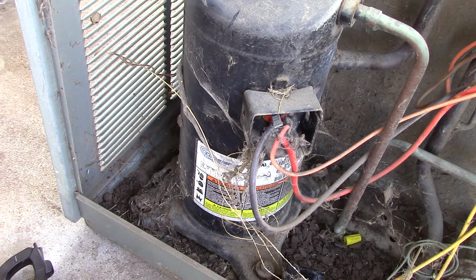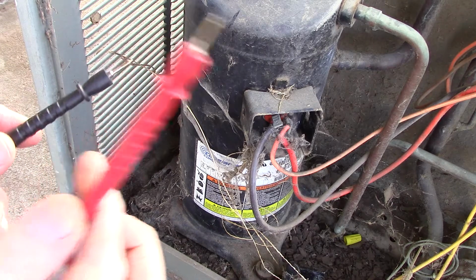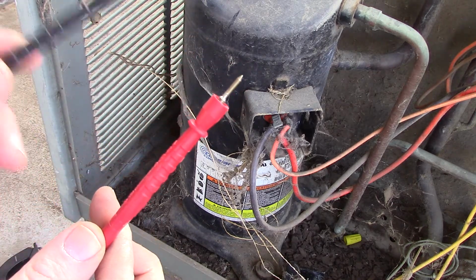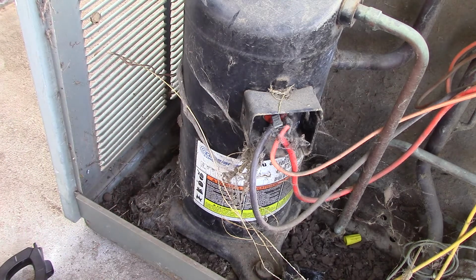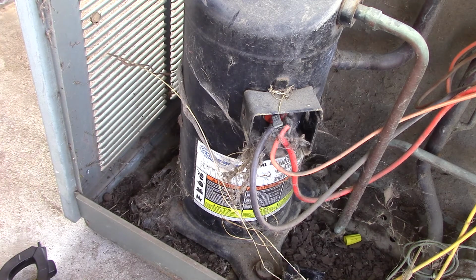You're trying to look for any OL. So you're going to go from run, common, start, or start, common, doesn't matter, and see what you have that way. If you get an OL between run and common and OL between start and common, congratulations. The internal overload has opened on here. If the compressor is hot to the touch, the internal overload is doing its job. If the compressor is cool to the touch, the internal overload is actually bad. It's a little sensor embedded in the motor windings that opens up to kill power to try to save the compressor. Okay, so that's where a lot of that's going to come into play.